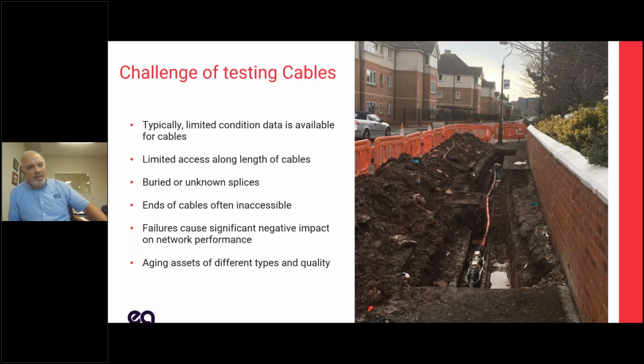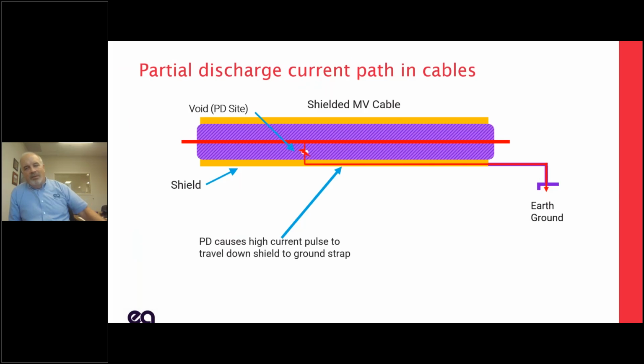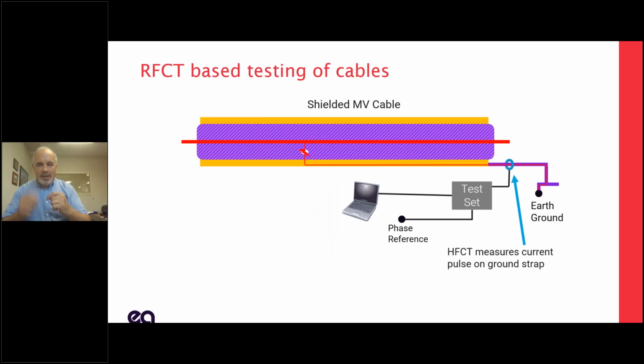If we can get to the ends and test from the ends in, we can find partial discharge anywhere in the cable. So the mechanism for partial discharge testing in cable is somewhere along the line you're going to have a discharge current. That discharge current is going to try and find a path to ground, and that path to ground is through the shield. So if we have this current path going down the shield and we can put an HFCT, or high frequency current transformer, around that ground strap, then we can do a test, and we can test for parts of the cable that may not be accessible.